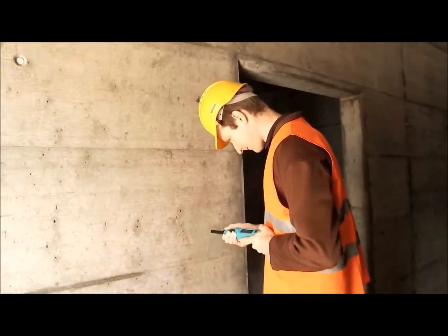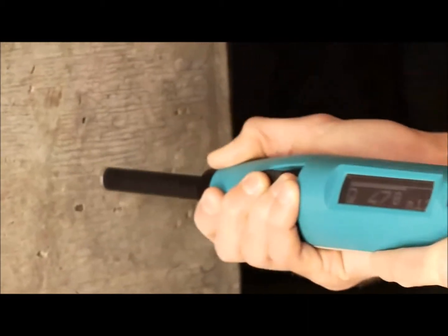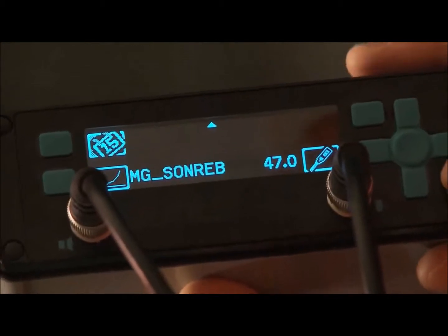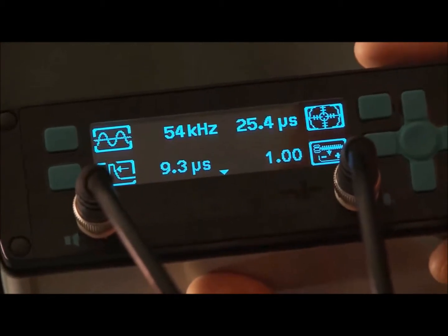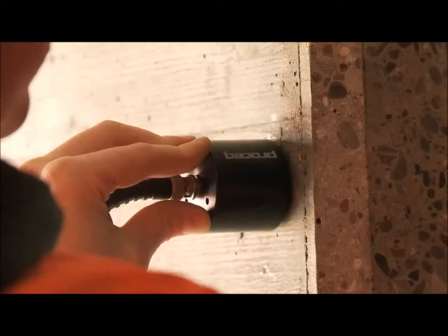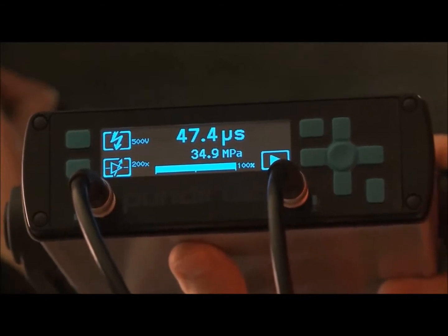It has been proven that rebound hammer measurements may be combined with ultrasonic measurements to give even better estimates of the in situ compressive strength. Here we can see the SilverSchmidt being used together with Proceq's Pundit Lab Plus instrument to determine compressive strength on site using the SONREB method.